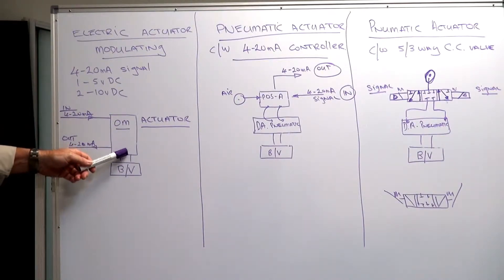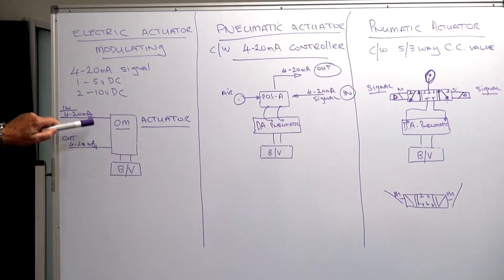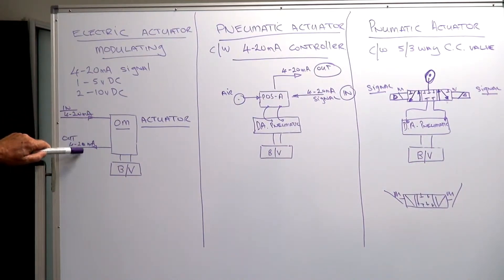At the same time it will give an output signal that will give a 4 to 20 milliamp to feed back to your PLC. This will confirm to the PLC the actual positioning of the ball valve in relationship to the input signal. It's a servo loop feedback to the unit.